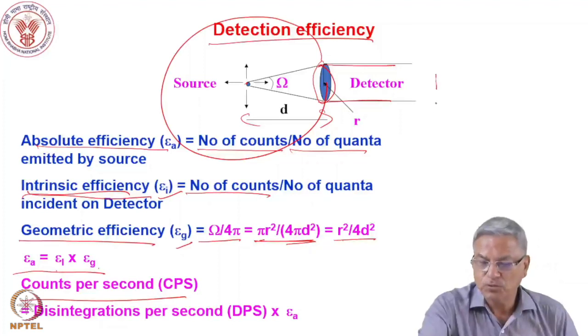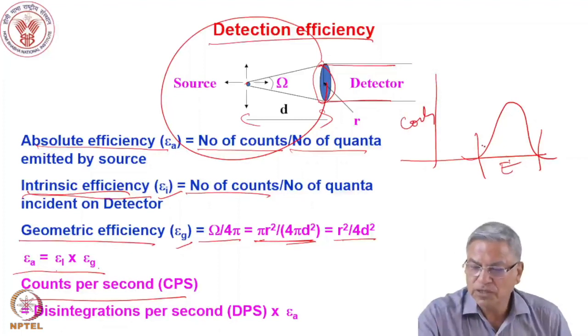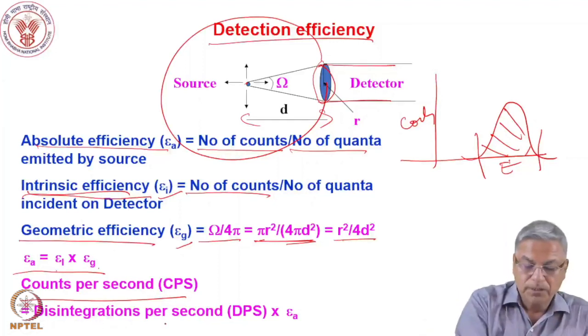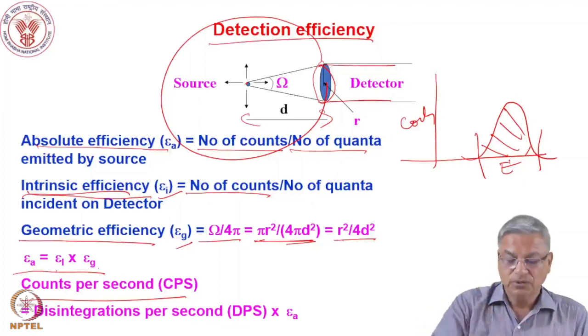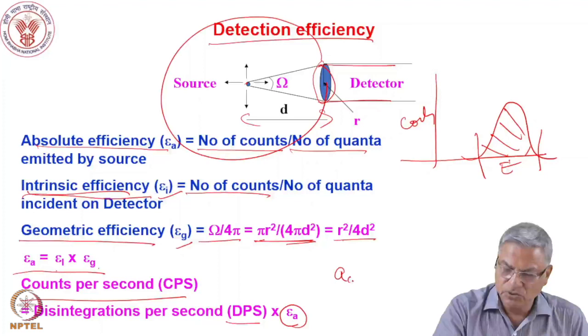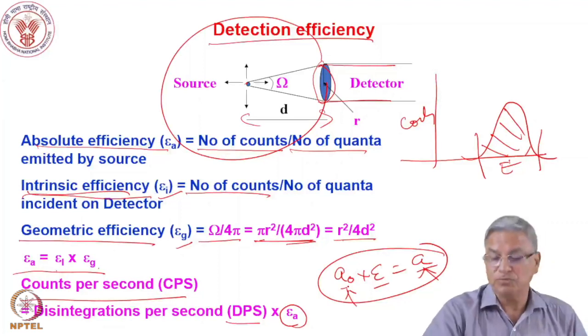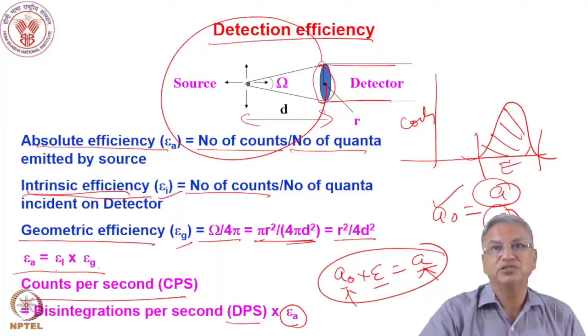Absolute efficiency equals the number of counts in the detector system divided by the number of quanta emitted by the source. For example, if a source emits 100 photons per second and your detector counts some fraction of those, that fraction is the absolute efficiency. In practice, absolute efficiency is used with a standard source. The geometric efficiency depends on the geometry of the detector system; the intrinsic efficiency depends on the detector material and the energy of the radiation. If you know the count rate and the efficiency, you can find the disintegration rate: A₀ = counts per second divided by efficiency.